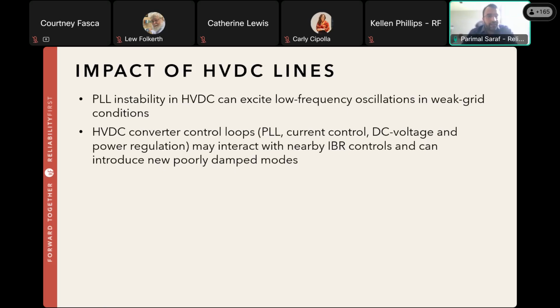And this is the last technology that I'm going to talk about today, which is HVDC lines, high voltage DC lines. Essentially, they have been proposed as an alternative to AC lines because they have very low losses, and they have been used to interconnect different interconnections. However, these HVDC lines are also based on control algorithms, and they also use the PLL, the phase lock loop, to track the parameters of the grid in order to run their controls.